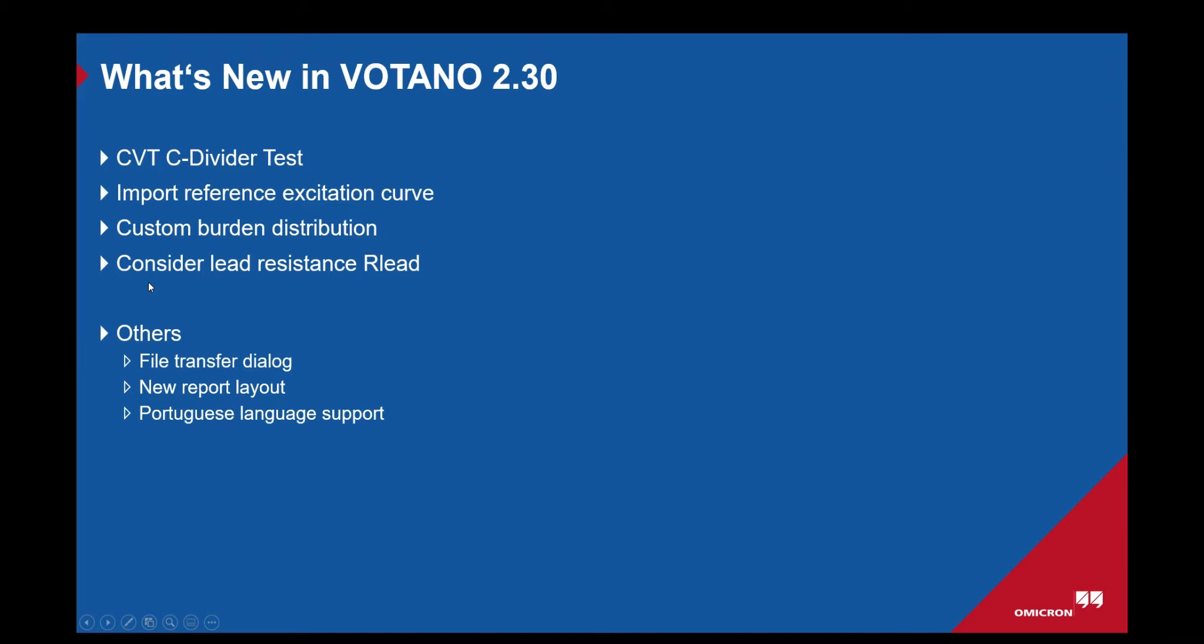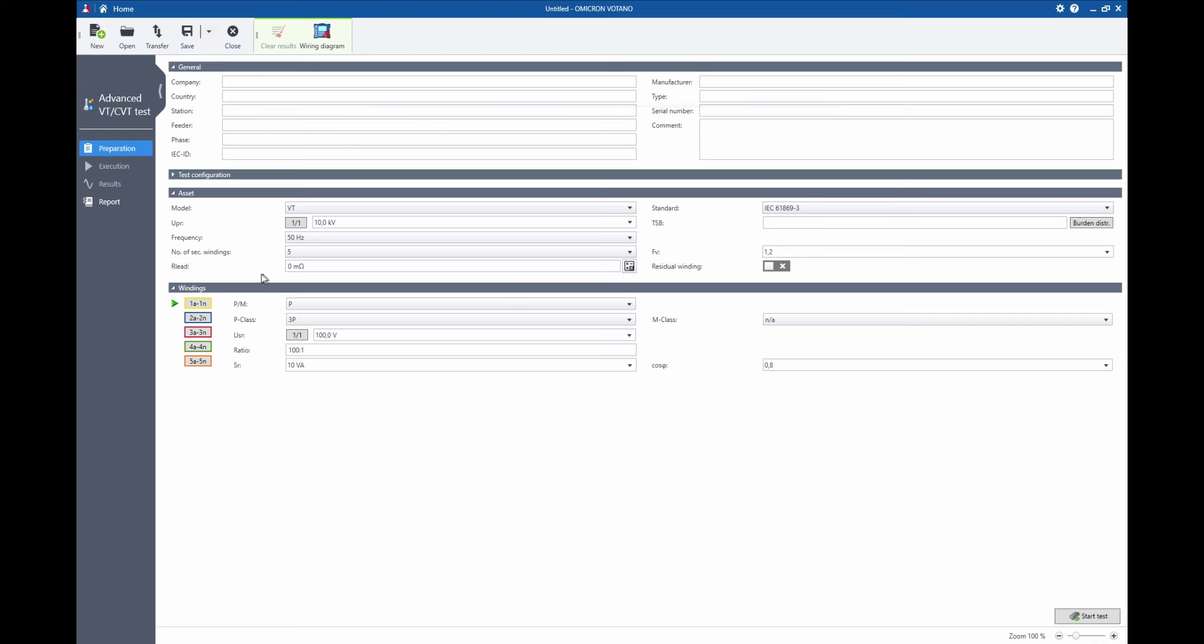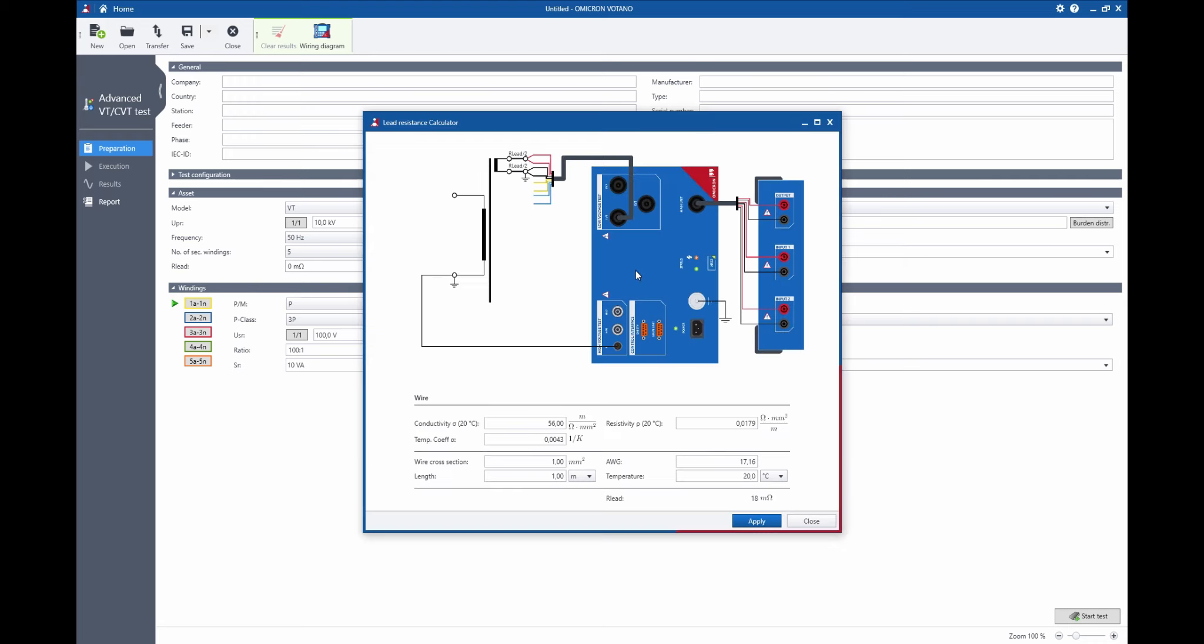We've also added a feature called consider lead resistance. This one is available here and it's best illustrated like this. If I have a situation where it's not possible to perform our measurement directly at the secondary winding but we need to do it from, for instance, a junction box, we have an additional voltage drop here which is called R lead.